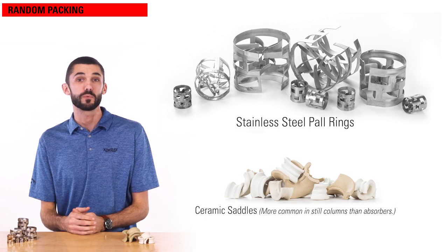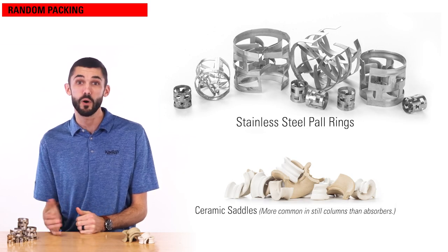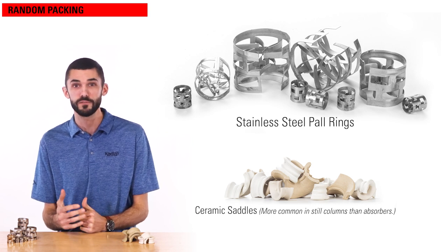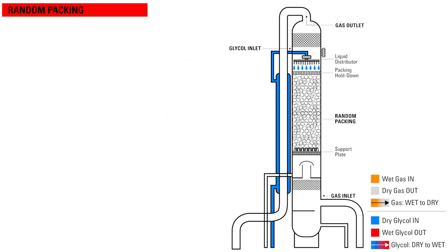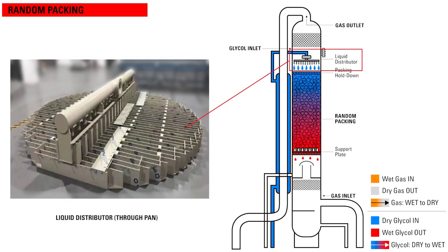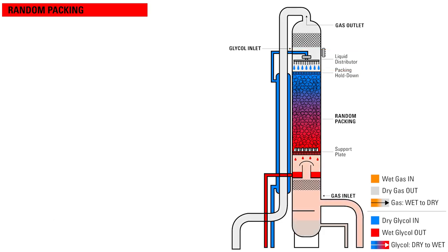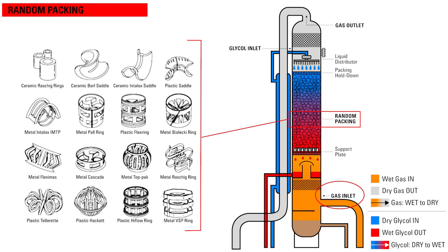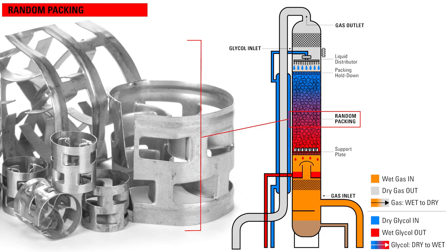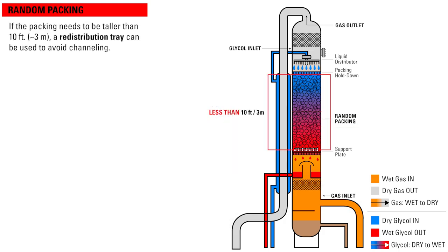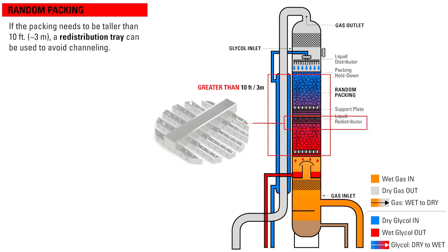In an absorber with random packing, the tower is filled with stainless steel Pall Rings or ceramic saddles. This random packing fills the tower and randomly falls into place. The dry glycol entering the top of the tower must flow over, around, and beside all of the packing, which distributes the glycol evenly through the tower. The gas enters towards the bottom and travels upward, contacting the glycol as it makes its way down, which absorbs the water from the gas. If the packing needs to be taller than 10 feet, a redistribution tray can be used to collect the glycol and redistribute it evenly through the tower to avoid channeling.